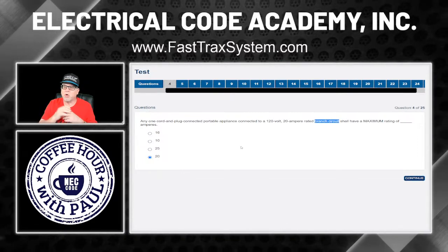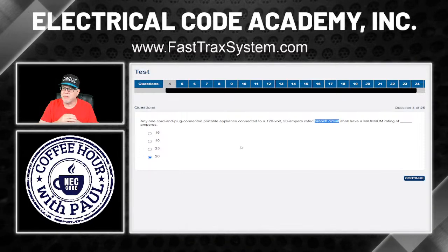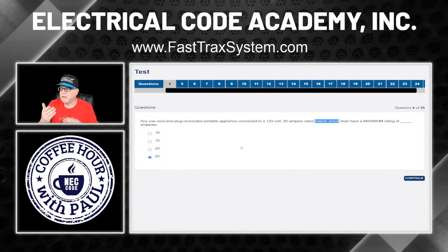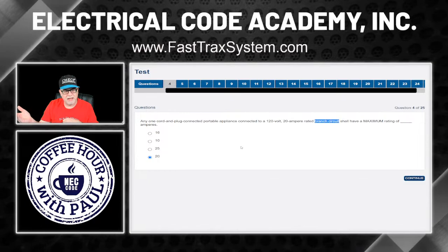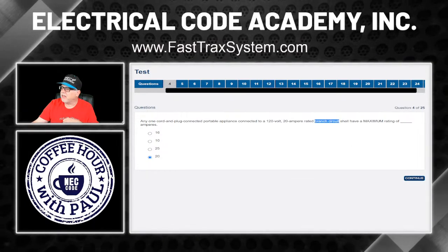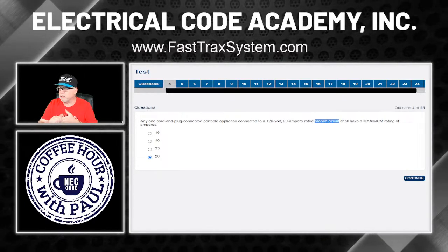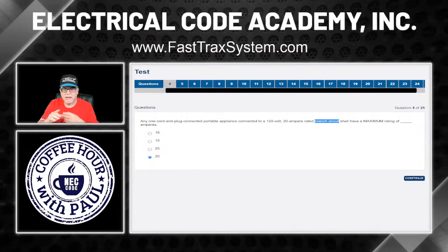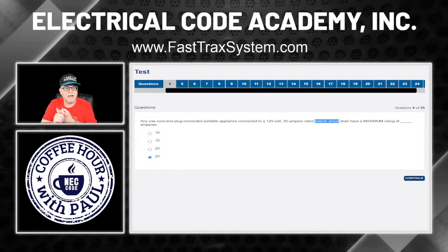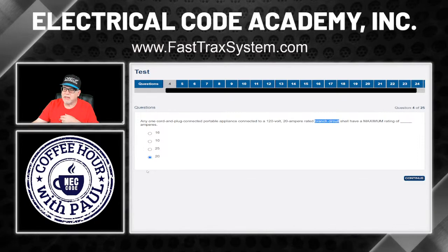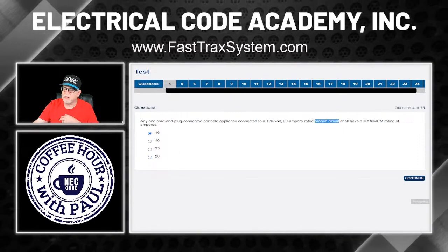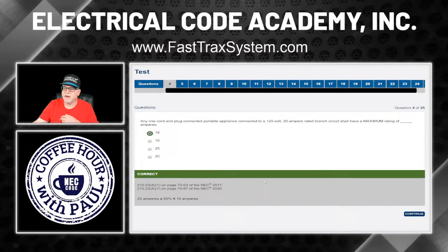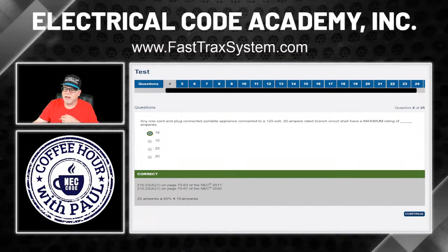But if you have a cord and plug connected portable appliance plugged into a 20 amp circuit, we just read that 210.23(A)(1) says you have to limit it to 80% of that. So 20 times 80% is actually 16. Let's see if we're right. And there you go. 20 times 80%.